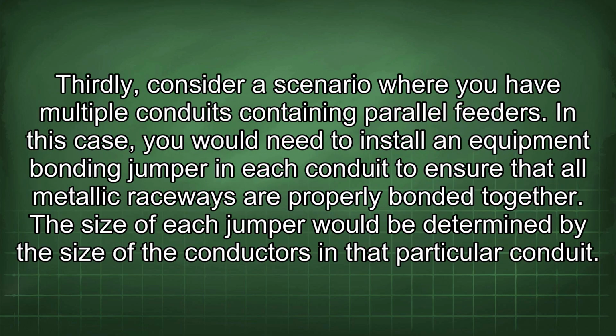Thirdly, consider a scenario where you have multiple conduits containing parallel feeders. In this case, you would need to install an equipment bonding jumper in each conduit to ensure that all metallic raceways are properly bonded together. The size of each jumper would be determined by the size of the conductors in that particular conduit.